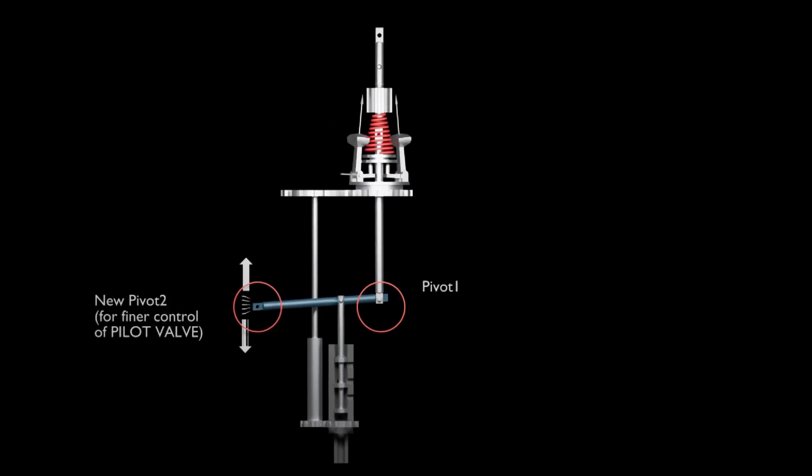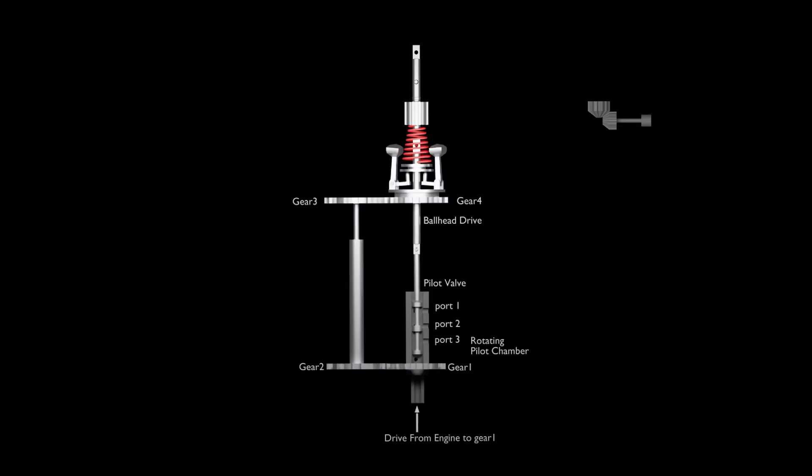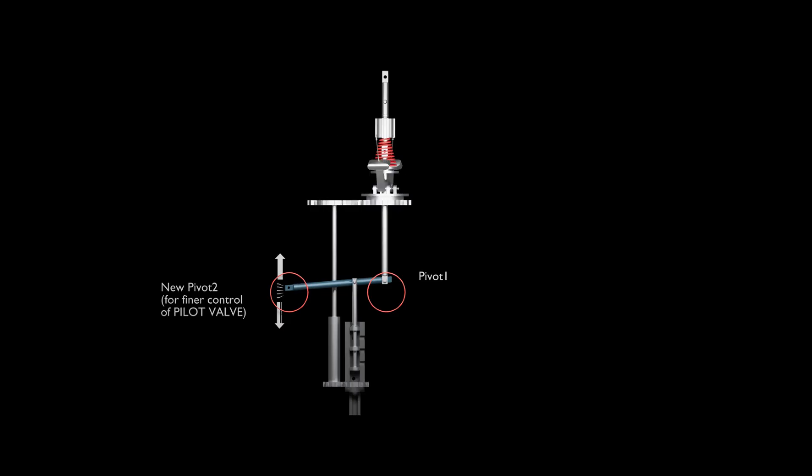Enter the compensating mechanism. Compensates for the time lag that engine takes to accelerate or decelerate due to its rotational inertia when fuel rack changes. Flyweights are blind to this time lag. They see only the instantaneous rotational speed and set pilot valve accordingly. A second simultaneous feedback to pilot valve is achieved by disconnecting the direct speeder rod and pilot valve connection. Instead, a new floating lever 31 is introduced.